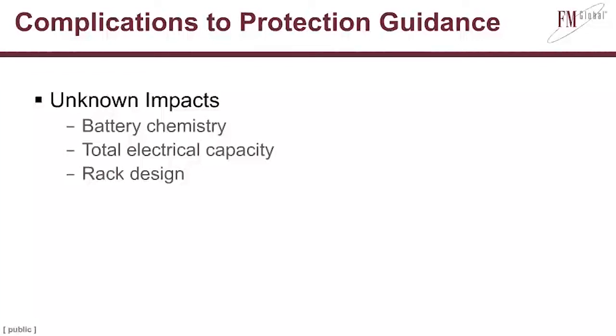It means you probably have to have some other means of getting hot gas out of the rack, such as a chimney. And if the fire service arrives and they try to hit the energy storage system with a fire hose, they're going to be hitting a metal door. So such a simple change can have a fundamental impact on the hazard and our ability to suppress or fight the fire in the first place, which means that there's no real easy way to generalize.